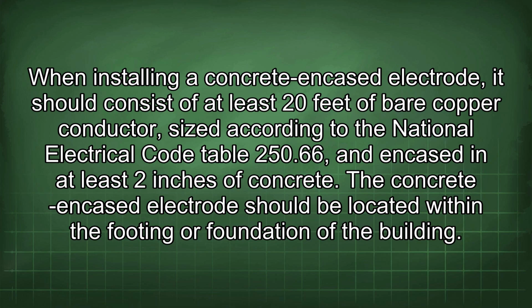When installing a concrete encased electrode, it should consist of at least 20 feet of bare copper conductor, sized according to the National Electrical Code Table 250.66, and encased in at least 2 inches of concrete. The concrete encased electrode should be located within the footing or foundation of the building.